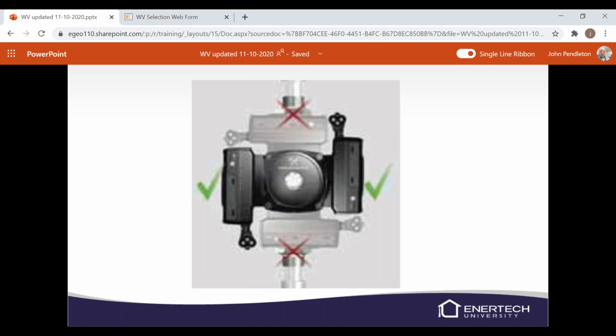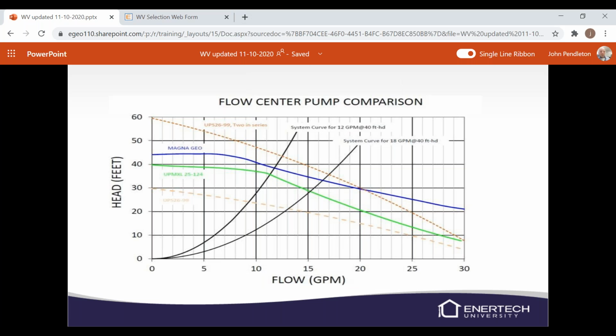Make sure you're installing it in this configuration, never with that electrical box on the top or the bottom, always on the sides. And here is basically the flow center comparison. The dotted brown line is the 2699s. The Magna Geo, which is the 32-140, the older pump, is in the blue, and the newer, the 25-124, is the green line there. So you can see we're not able to flow quite as much, but hopefully it won't be an issue. If it is an issue, we'll just have to add an external pump into your system.